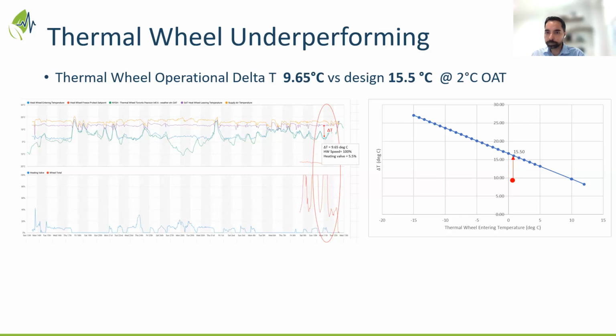So Amandeep, did you do this testing on all 10 hospitals that took part in this? Yes, this analysis on underperforming of the wheel was done on our hospitals. For some hospitals we could not do it because the trends were not available, but for the majority of hospitals where we had the trend, we did that analysis. And did any of them come out close to design values? Were any running close to where they should be? Yes, most of them came close to design values.